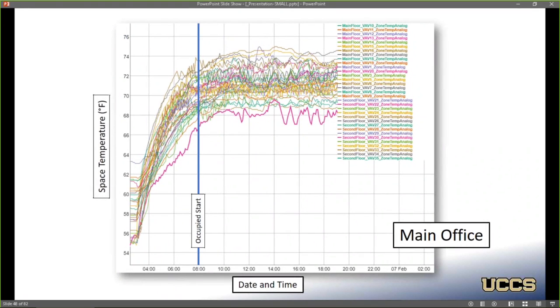And here's a trend graph of all 34 VAVs and kind of how they recovered that morning with the occupied start time of 8 o'clock. And you can kind of see the trend of the good and the bad. It's kind of a spread, but most of the spaces were up to right around 69 to 70. Some were even up to over 72 at that time, but there were some that did struggle to get there in time. And this wasn't an excessively cold night. It was probably around 20, 25 degrees that night, so the problem would have probably been more apparent if it was a 0-degree night.